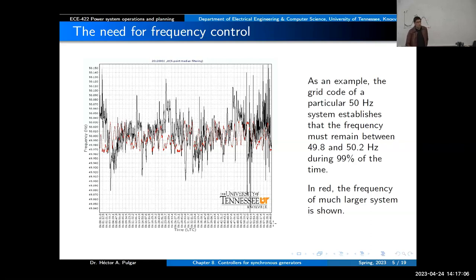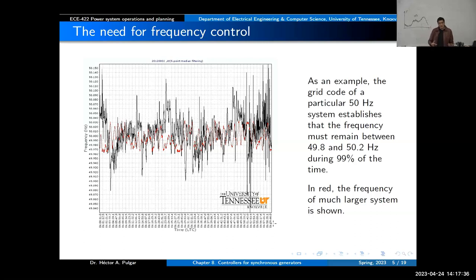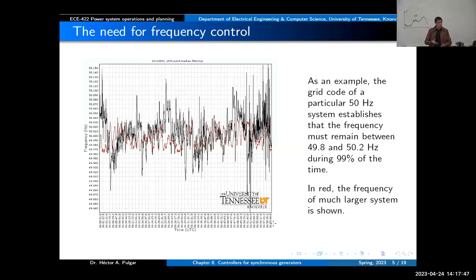Synchronous generators are very good for controlling reactive power and voltage. We can control the field winding current, which has to do with the induction of voltage and reactive power. Wind turbines, depending on technology, can provide some reactive power as well, but that requires increased investment because the power electronic devices need to provide more current capability to provide more reactive power support to the system.